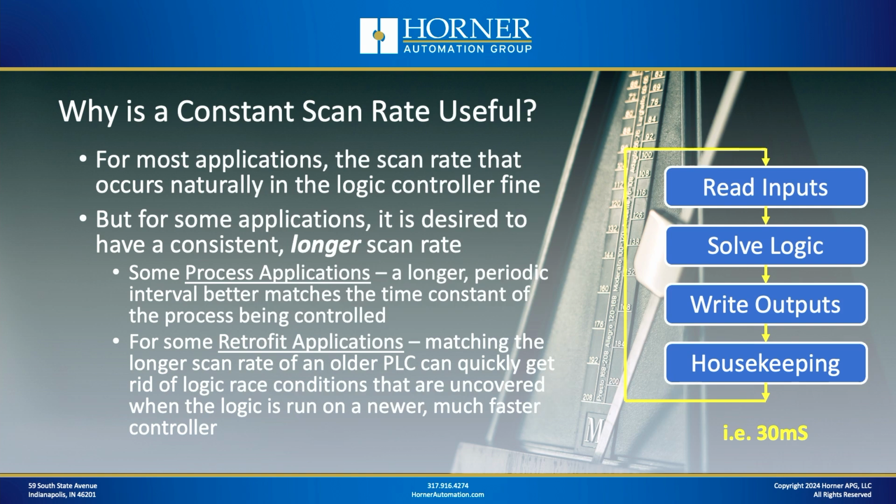So again, you don't need to lengthen the entire scan just to take care of that PID loop. However, the one very practical application where you may want to use this is a retrofit application. Maybe you've got a machine that's 10 years old and you're updating the controller to a new controller that might have a scan rate 10 times as fast as the old one. Shouldn't be a big deal, right? You're getting faster. However, after the upgrade, you might find that certain machine sequences aren't happening properly or they're getting stuck.